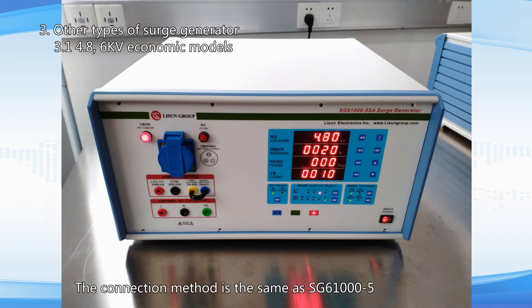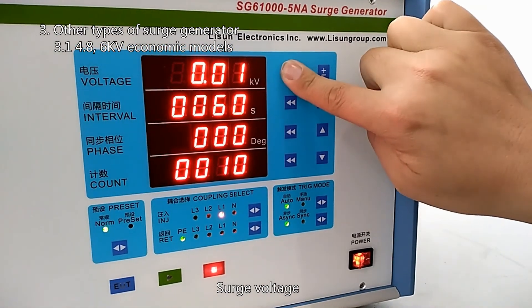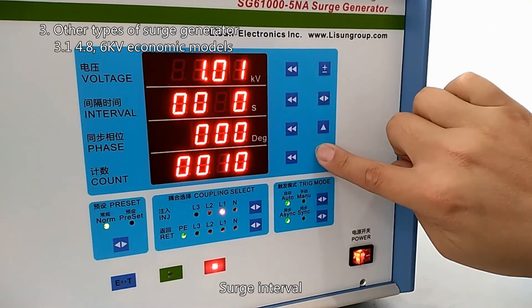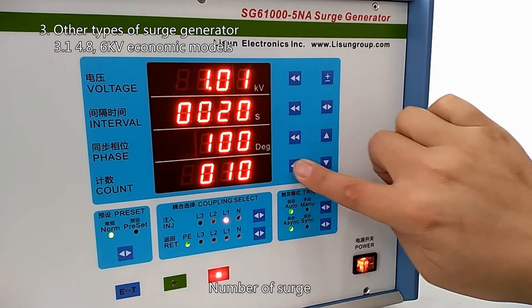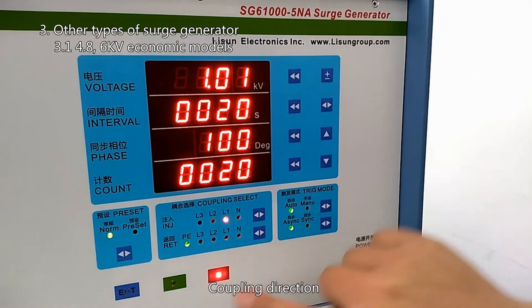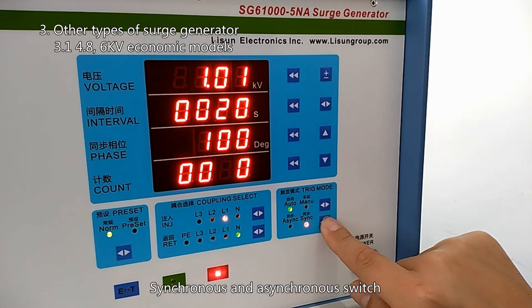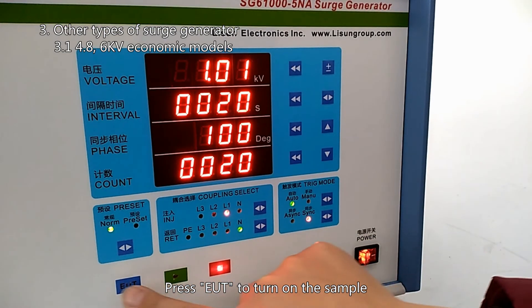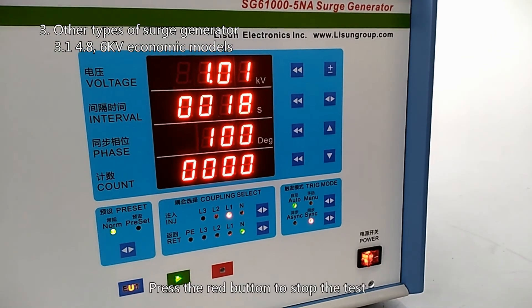The connection method for the button model is the same as SG61000-5. Set surge polarity, surge voltage, and surge interval. No other parameters need to be modified. Turn on the air switch, press EUT to turn on the sample, press the green button to start the test, and press the red button to stop the test.